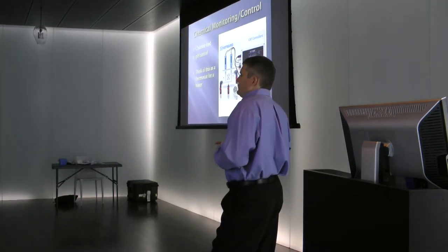Those probes, how much maintenance and calibration do they require? About every 2 months you want to clean them. You want to take them out and do a cleaning on them. They only last about 2 years, and that depends on some environmental things, like how bad the water chemistry is going through it all the time, or whether it's going through too fast and wearing out the KCl in there.